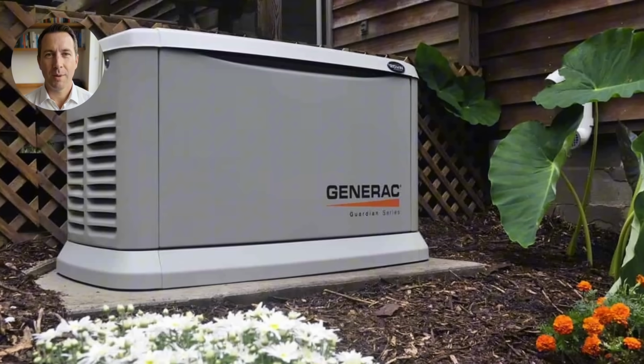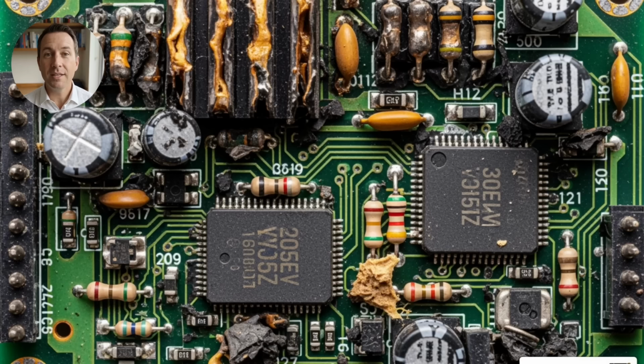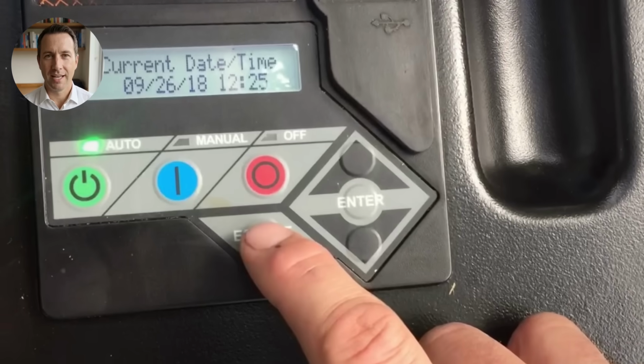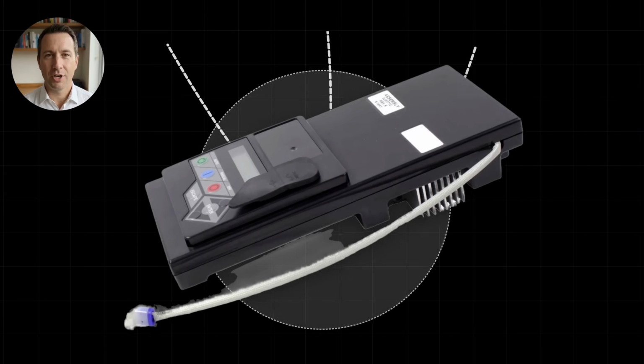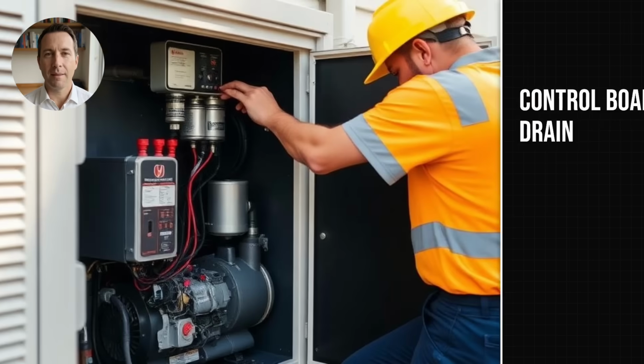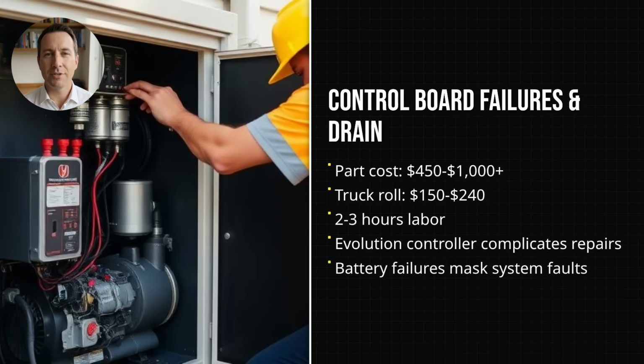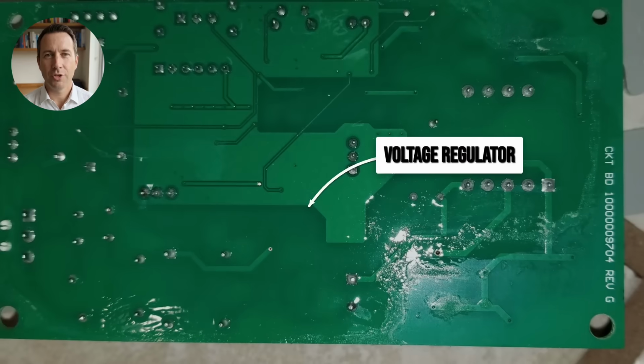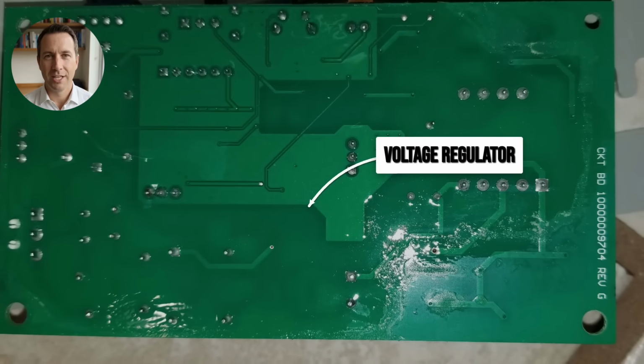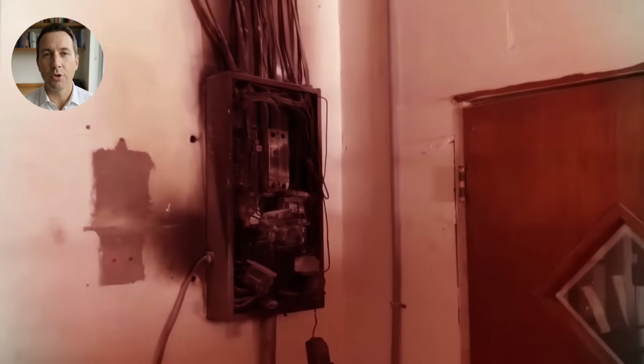And if that were the only problem, Generac might have survived it. The control board failures are arguably worse because they're more expensive and harder to diagnose. The Evolution controller handles voltage regulation, battery charging, and system monitoring. When it fails, you're looking at $450 to over $1,000 just for the part, plus $150 to $240 for the truck roll, plus 2 to 3 hours of labor. And the voltage regulator is built into the motherboard, so you can't replace just the failed component. You replace the whole board or you don't fix it.